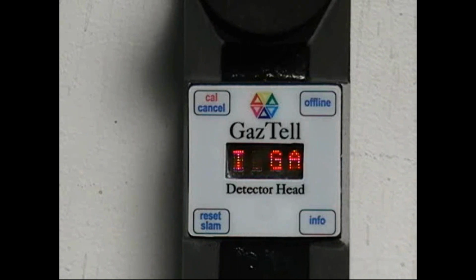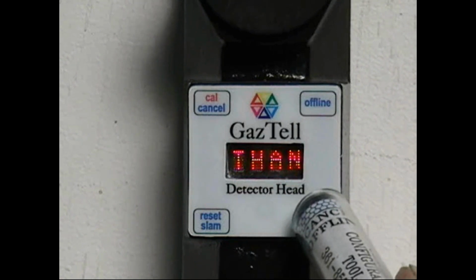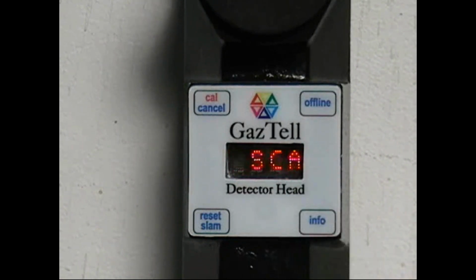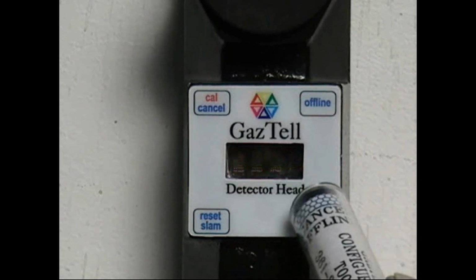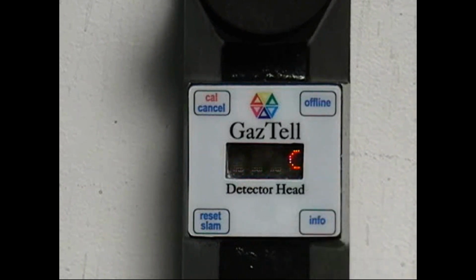Target gas is where you can choose another gas if one is loaded into the detector head. Methane is the default gas. Other scales can be chosen if the selected target gas allows it. Methane can be selected for % LEL or % by volume. Again, this can be performed by holding the calibrator over the info mark for 5 seconds.